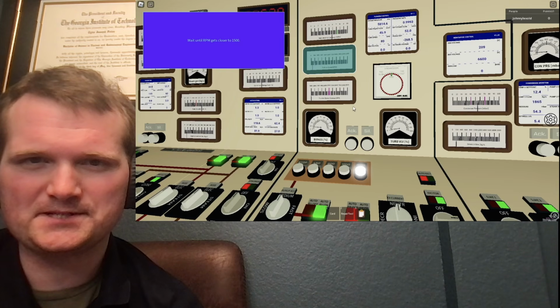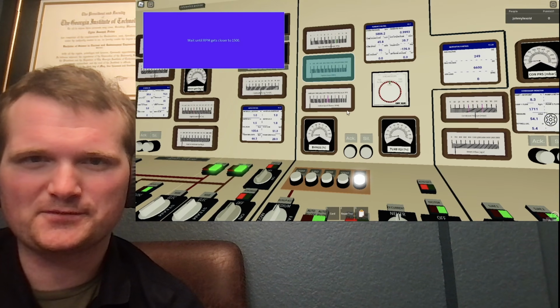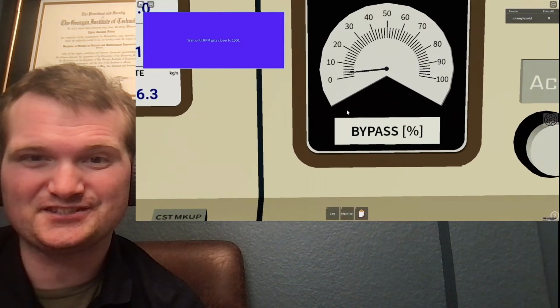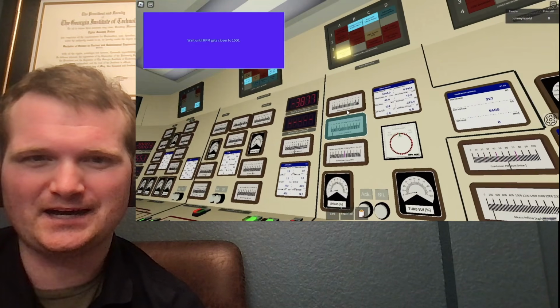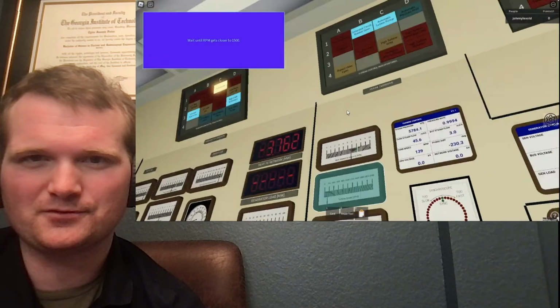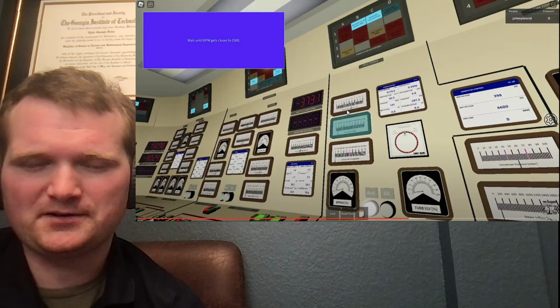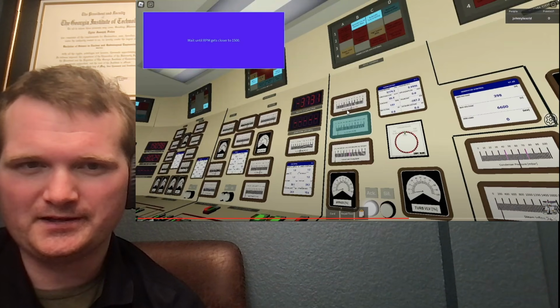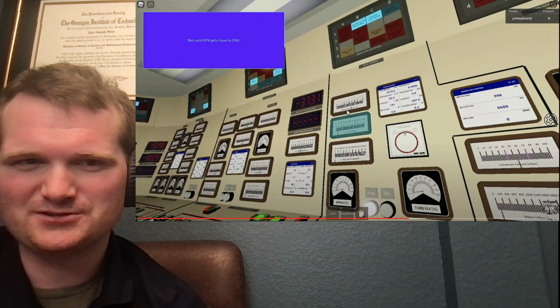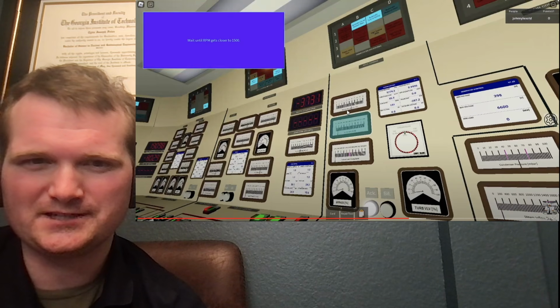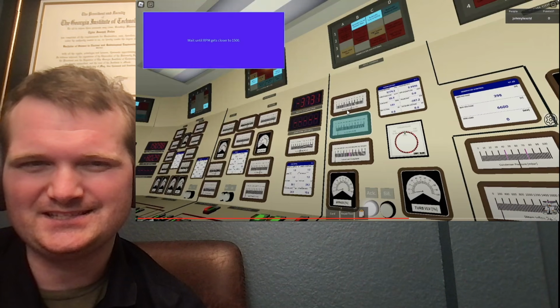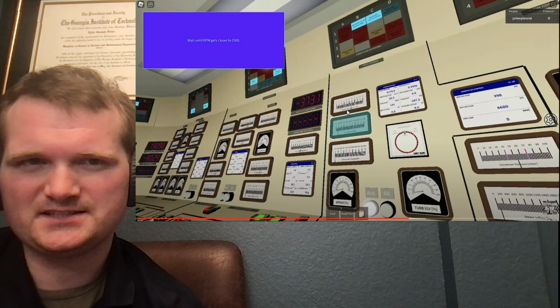And now spinning up the turbine to 1500 RPM. I wonder if there's going to be some speeding up here, because that takes a while. There's a whole science behind rolling the turbine. There's periods where you roll and then you wait, and then you roll and you wait some more until you eventually get up to 1500. At the plant I worked at, the number was 1800 RPM.